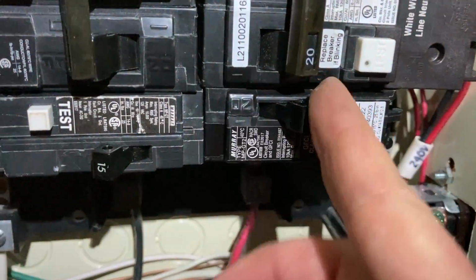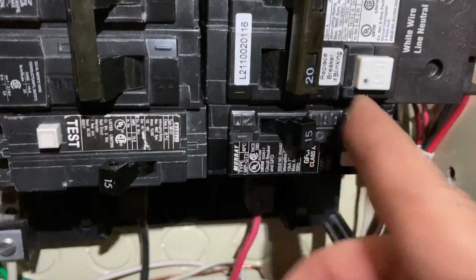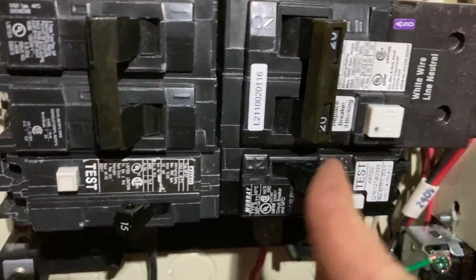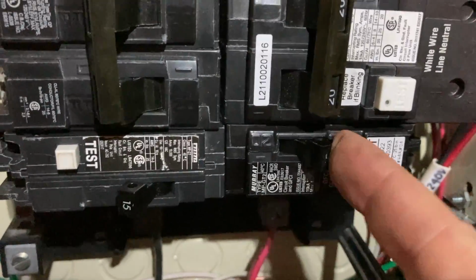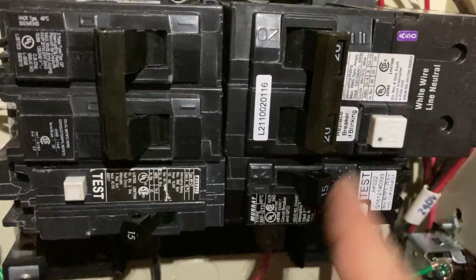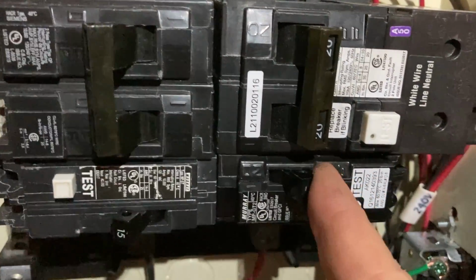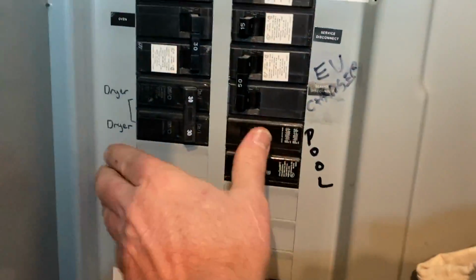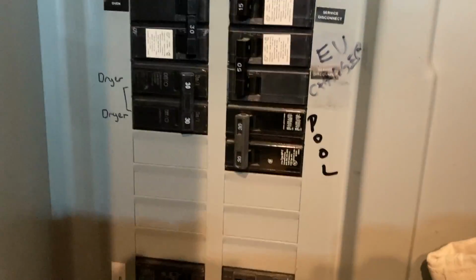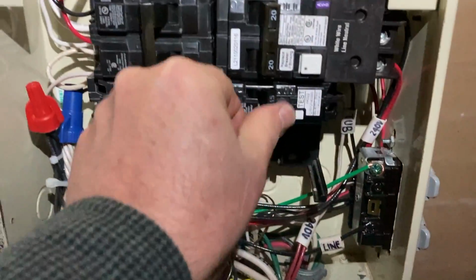These modern GFCI breakers are fail-safe breakers - they won't even turn on if there's no power. They actually have two current sensors in them, two current transformers: one to sense the power there and the other to sense the balance. Well, it didn't blow right away - that's good. Okay, let's see if we can fire up the hot tub now.